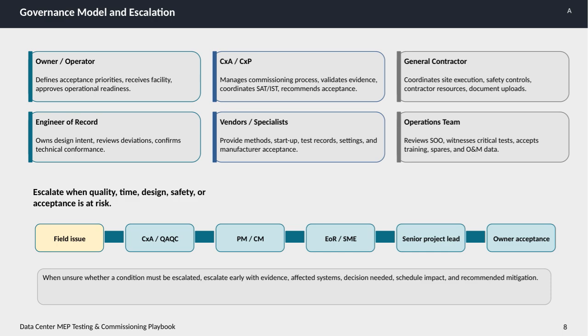acceptance. The general contractor coordinates site execution, ensuring safety controls are in place, managing contractor resources, and maintaining accurate document uploads throughout the process. The engineer of record owns the design intent, reviews any deviations, and confirms that the technical aspects conform to the design specifications. Vendors and specialists provide specific methods, handle startup procedures, supply test records, set equipment configurations, and issue manufacturer acceptances, all critical for verifying that systems perform as planned. The operations team reviews the sequence of operations, witnesses critical tests, and accepts the training, spare parts, and operations and maintenance data needed for ongoing facility management.